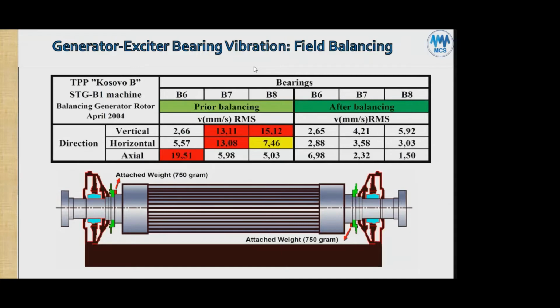And the field balancing, you can see the results prior to balancing and after balancing. We have bearing B6 and bearing B7 and bearing B8. B8 would be the bearing of the exciter. So B6 and B7 are the two bearings you see in blue color in front of you. And the vibration here is measured in millimeters per second.